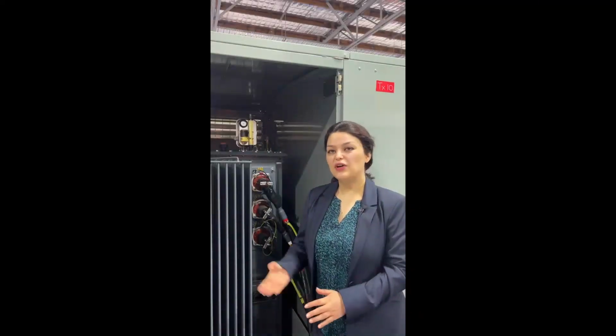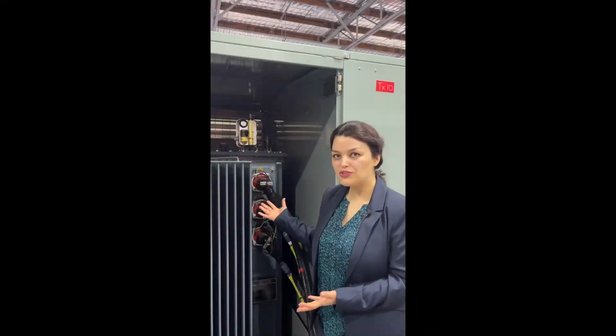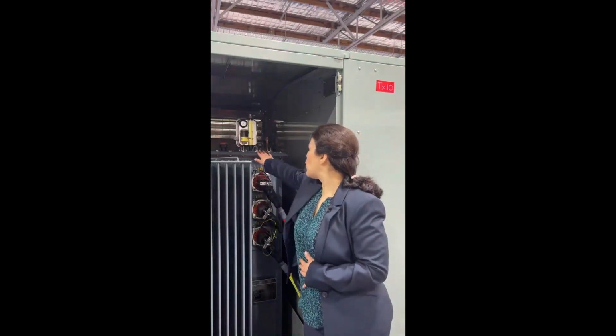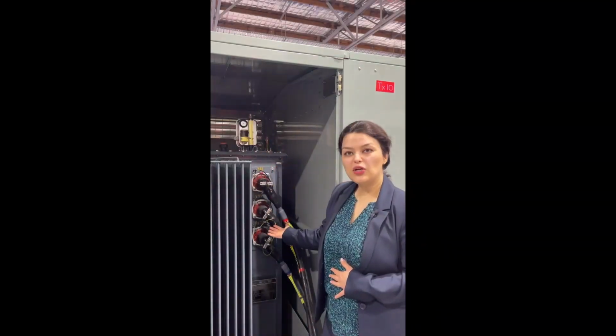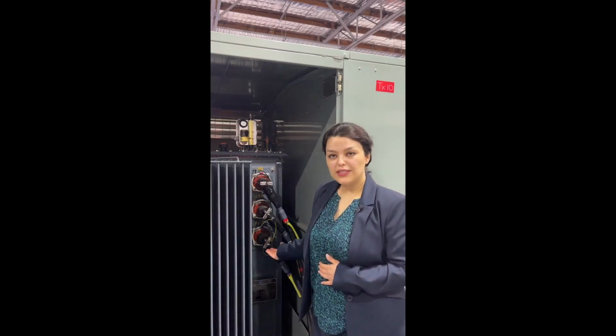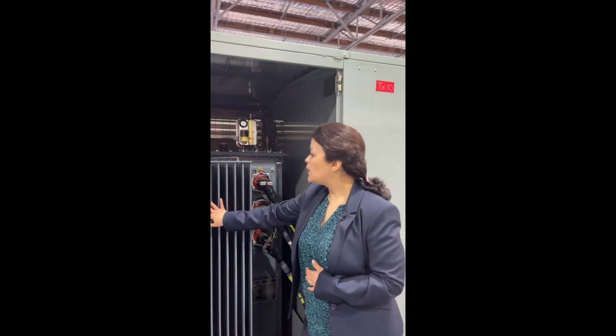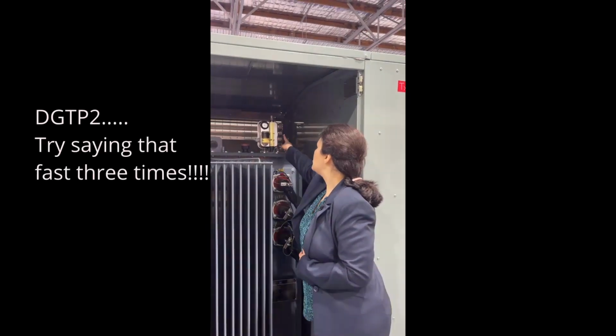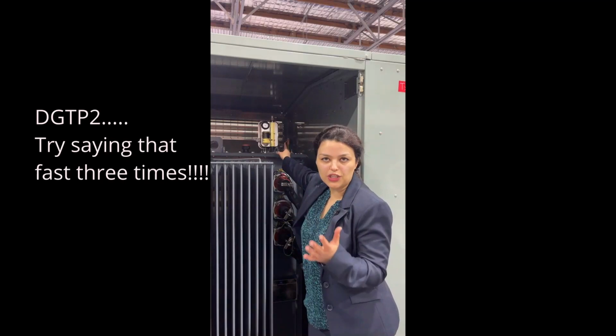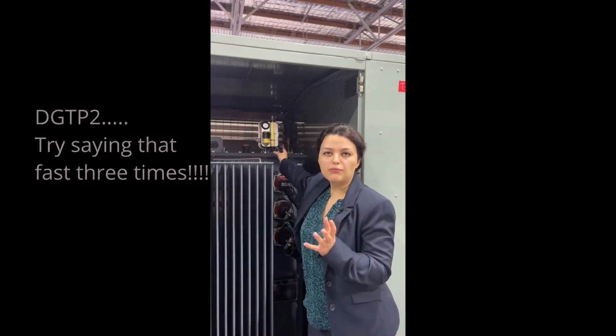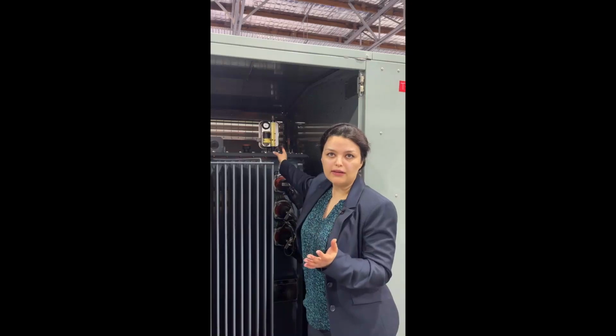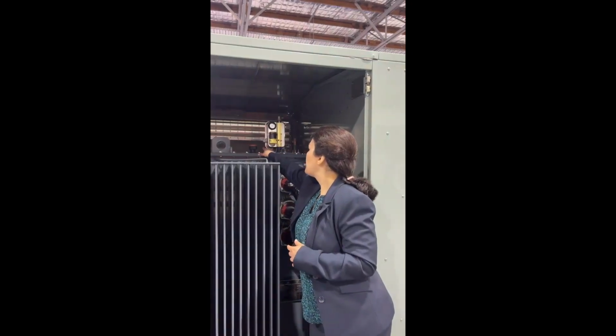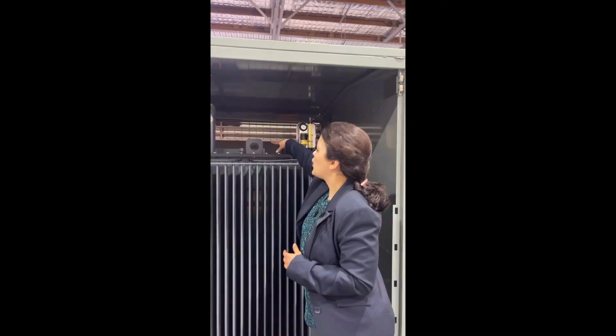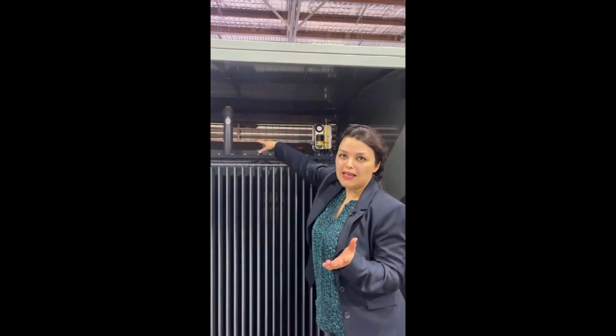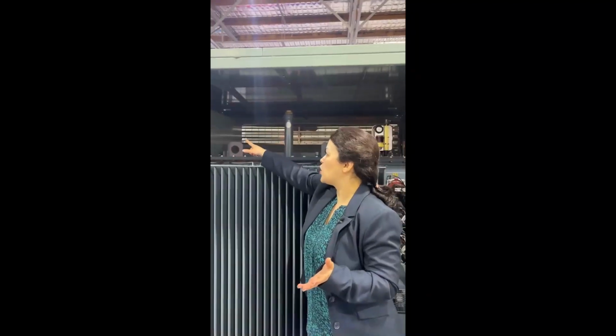Thanks, Nick. Here we are going to look at some of the physical construction of an oil transformer. What we have here is an oil tank. These are HV terminals using plug-in bushings with screened elbow connections. These are cooling fins. That's the DGTP2, which is the integrated protection device, which is monitoring temperature, pressure, and oil level. That's the off-load tap changer. That one is the welded lifting point for the oil transformer. That's the safety valve, and that's the LV cable box. Thank you. Back to you, Nick.